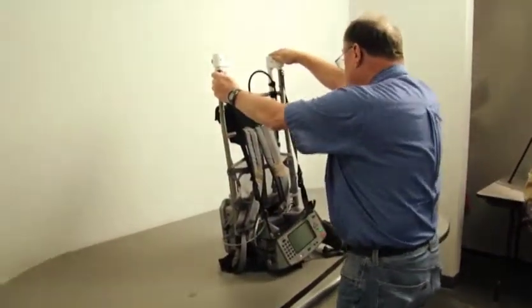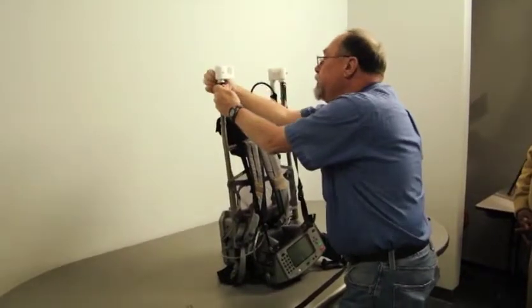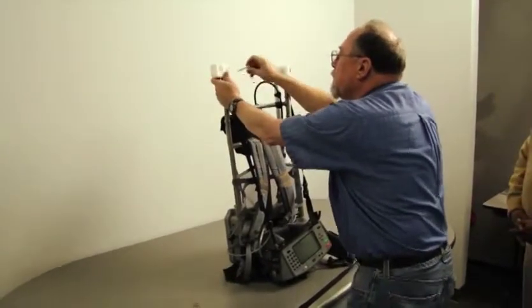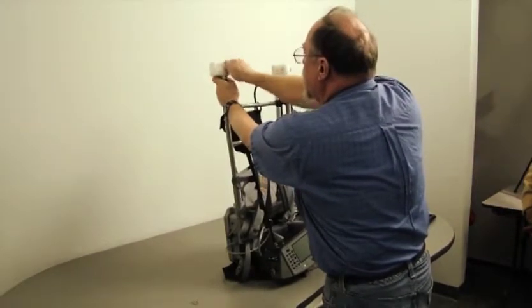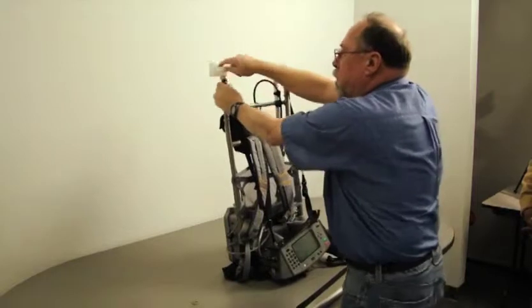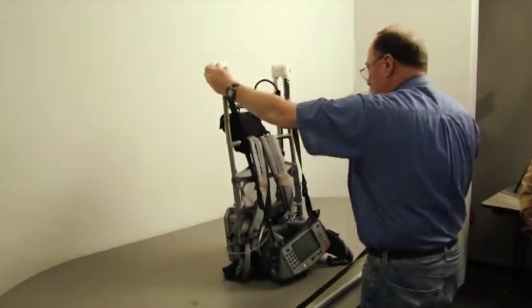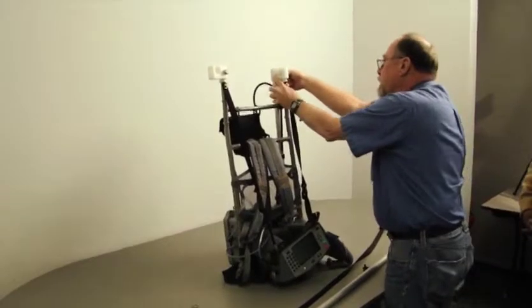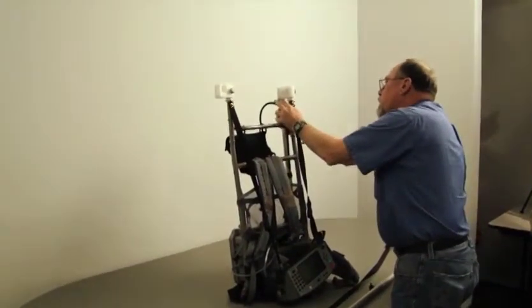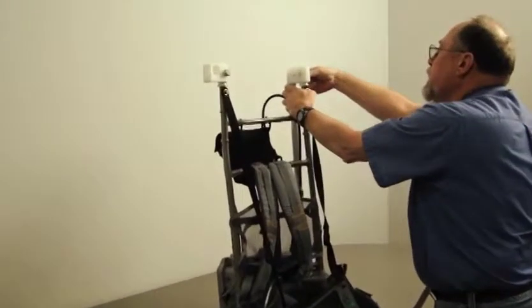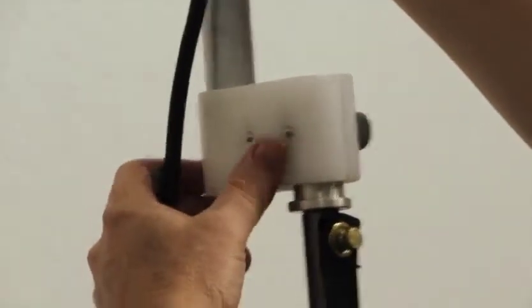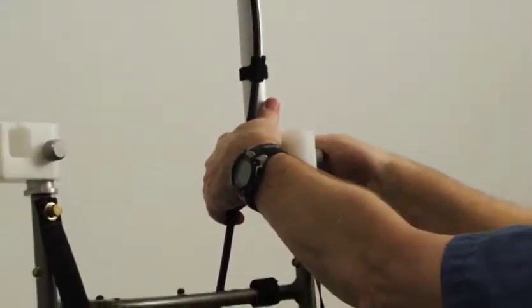We're going to set up the GPS antenna and the strap clamp or the strap fixture. And the strap fixture goes with the open end outboard of the backpack. The GPS, loosen the screws for the GPS. Once the screws are loosened, you can gently slide the GPS tube out of the bracket, turn it around and lift it, and put it in the bracket right side up.